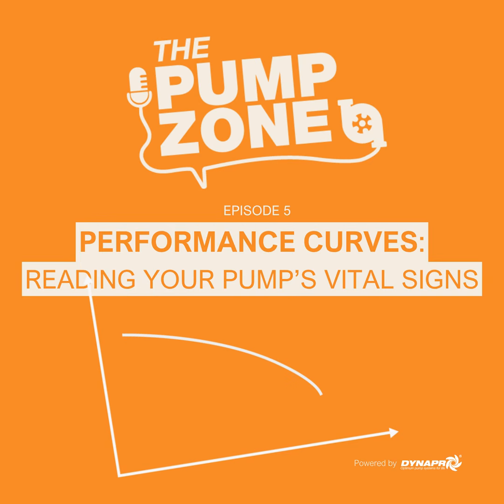It's kind of like a dartboard, right? Oh, dartboard. How so? The BEP is the absolute bullseye. The POR is that safe inner ring. But the AOR is the outer edge where you survive, but you're risking long-term damage if you hang out there too long. That is a perfect analogy. Because when you operate out in the AOR to the right of the BEP, you get cavitation. And to the left of the BEP and the AOR, you get flow recirculation inside the casing, which creates unequal pressure. It puts this unbalanced force on the impeller. And that force causes the heavy metal shaft to literally deflect and bend while it spins, slowly crushing the bearings and shredding the seals. Slowly but surely. Frequent use out there causes premature wear to practically everything.